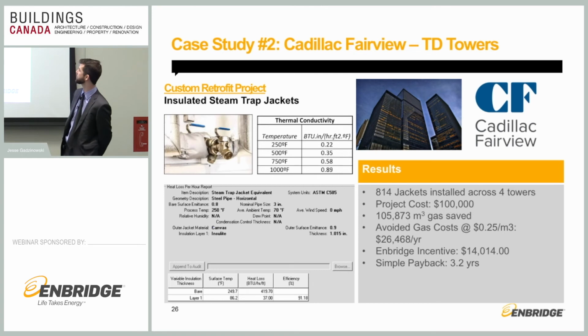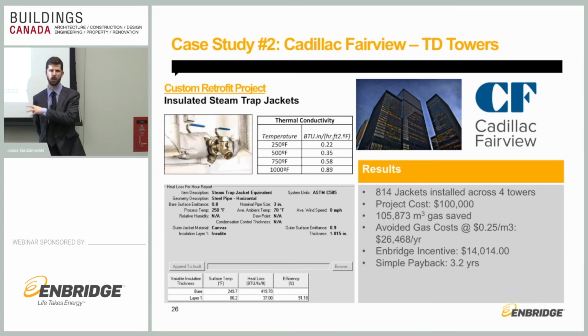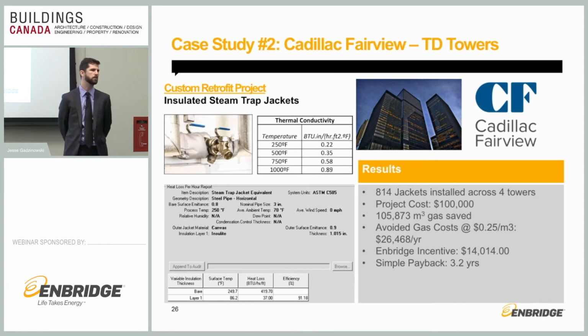Like I said, this was a large project for Cadillac Fairview. The total project cost was around 100 grand. They saved 105,000 cubic meters of gas. We gave them in total a $14,000 incentive, and the payback was 3.2 years. For 814 traps, the numbers look great, but most steam systems out there, you're seeing like 30 traps or 20 traps, things like that. So this is a great number, but I'm not sure if you guys are dealing with steam, but the incentives are good when it's that big, but it scales.